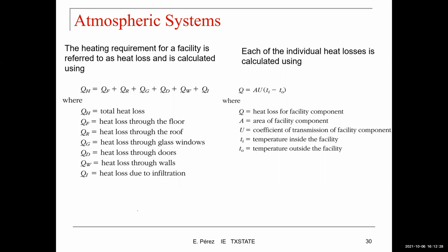So that heating requirement, or heat loss, has components: the heat loss through the floor, the heat loss through the roof, the heat loss through glass windows, the heat loss through the doors, the heat loss through the walls, and the heat loss due to infiltration.